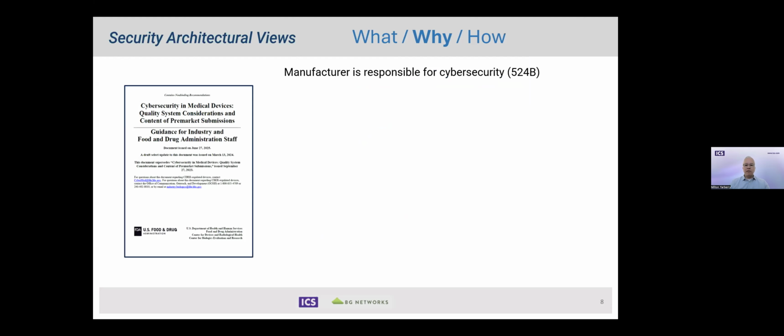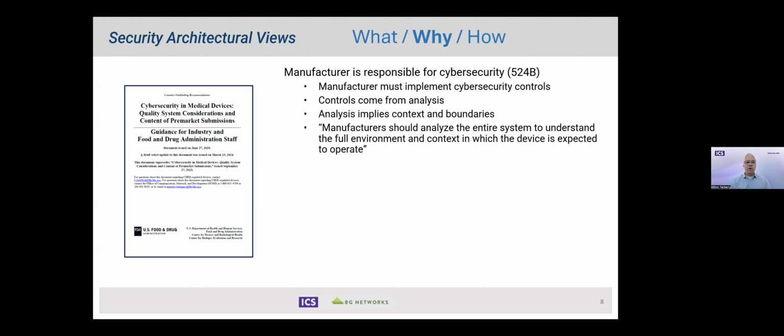So that was the what, moving from the what to the why. Why create these views? Well, 524B says that the manufacturer is responsible for cybersecurity, which means that you must implement cybersecurity controls in order to achieve security. These controls come from analysis, and analysis implies a context and boundaries.